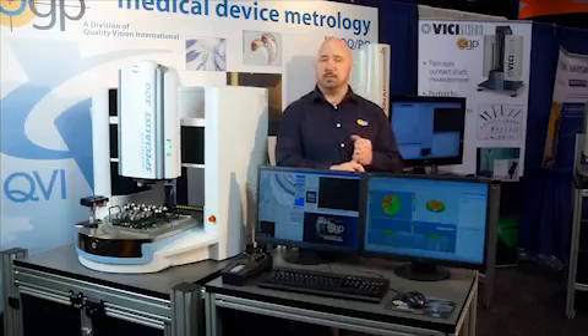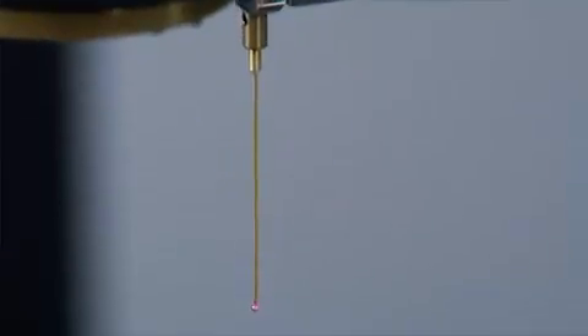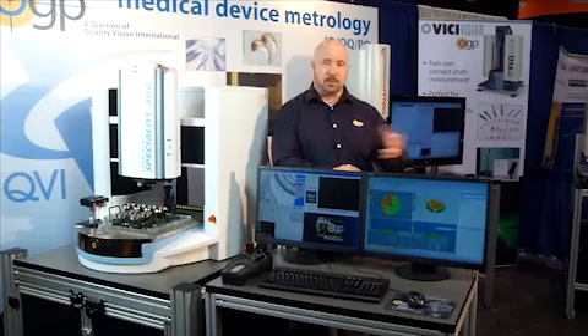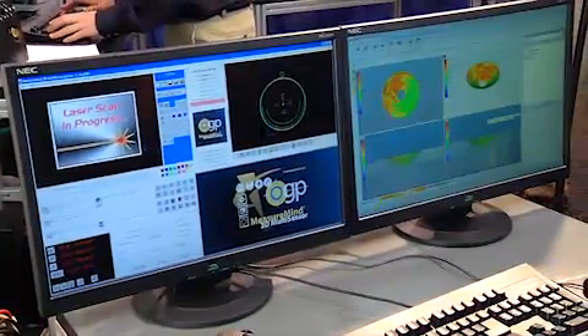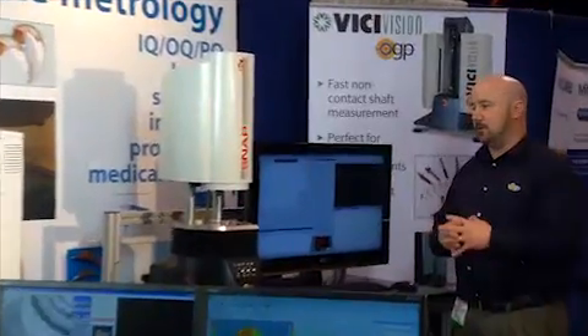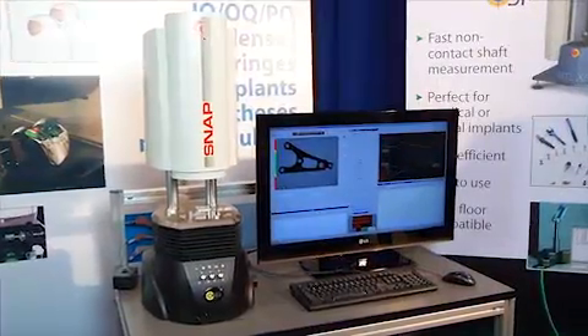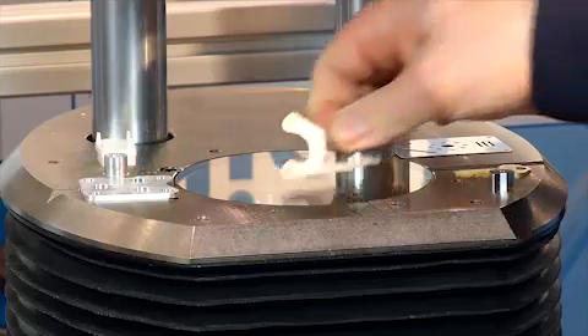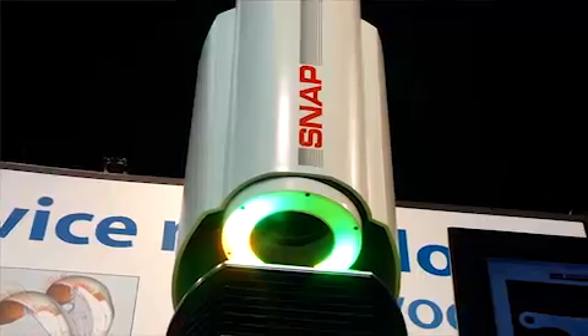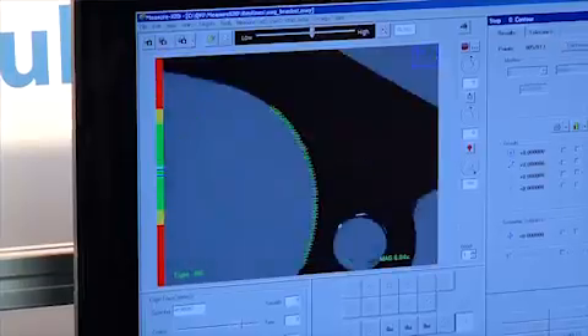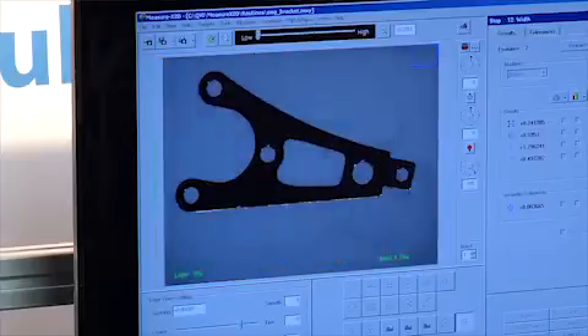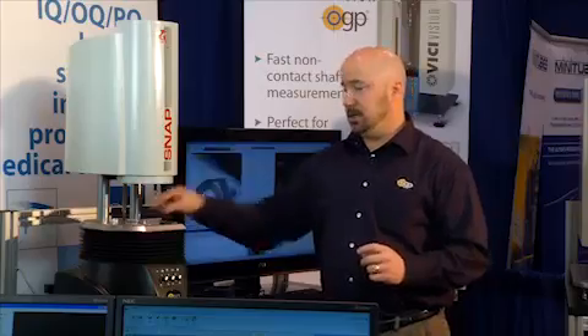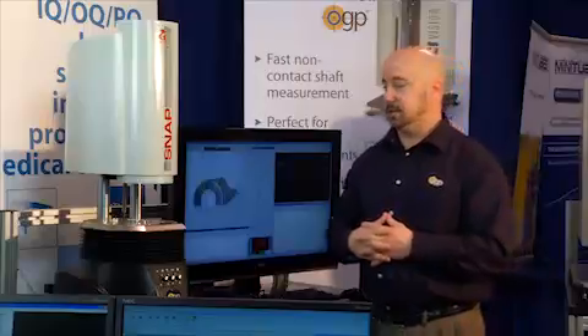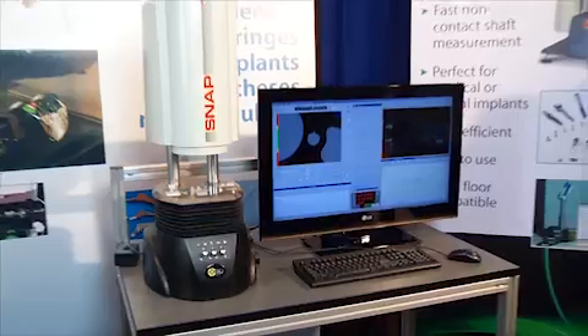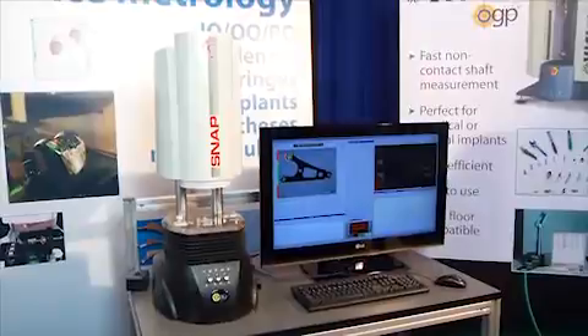This machine has multiple sensors, touch probe, laser, video, and micro probes to acquire the various measurements on the parts. We also have software that allows you to do 3D analysis on the part, which is shown here. The Snap is a product that we offer that is a digital measuring machine intended for very fast measurements. This handles 75 millimeter working area for parts that are small like this, a very fast, very accurate system. You can take a part, put it on the stage in any orientation, and it automatically detects the orientation and is able to do quick measurements on the part and output results very quickly.